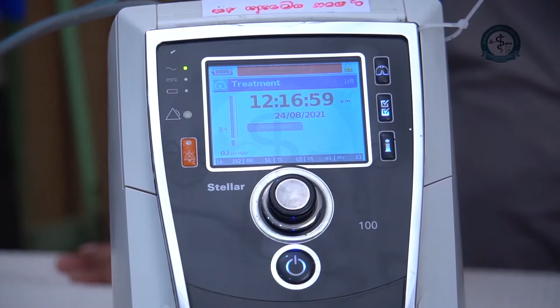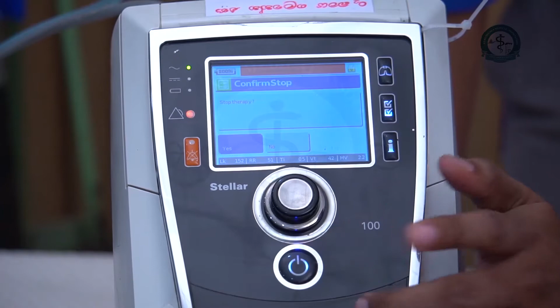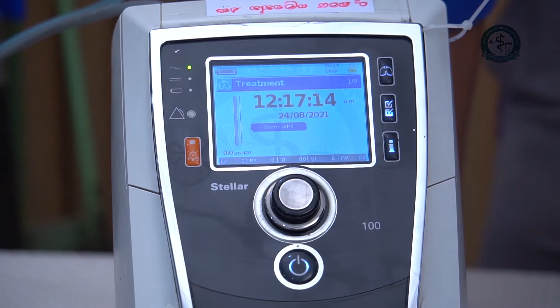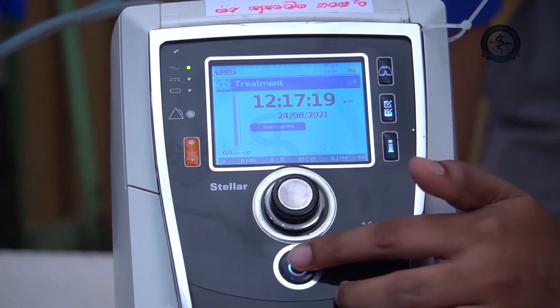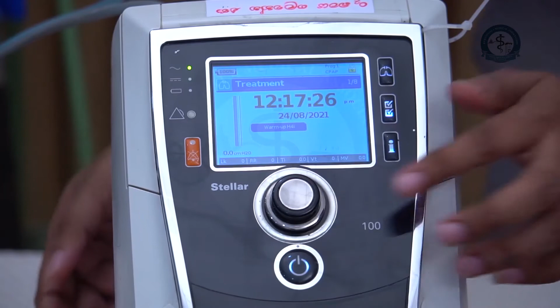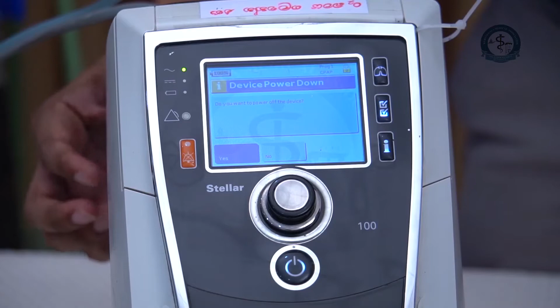How to stop ventilation? Press the on-off button on the upper surface. It will stop ventilation temporarily. How to switch off the unit? You need to stop ventilation before switching off the unit. So first press the on-off button on the upper surface and stop the ventilation. Then press the switch on the rear surface. Then a warning message will appear on the main screen and select yes for permanent switch off.